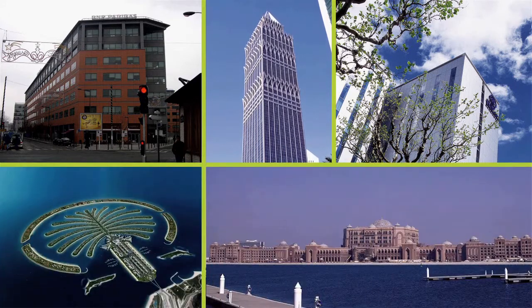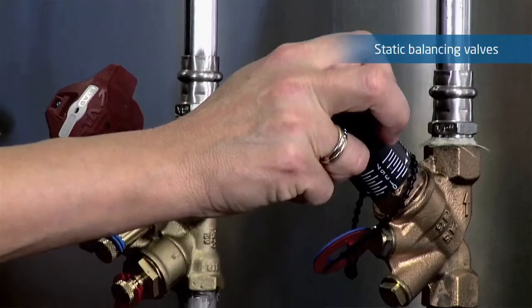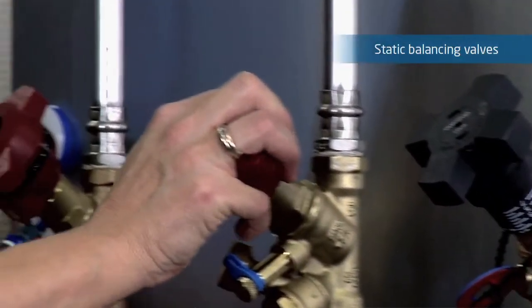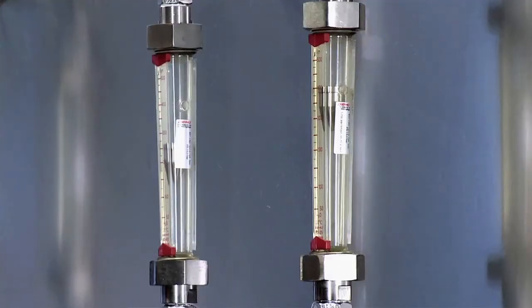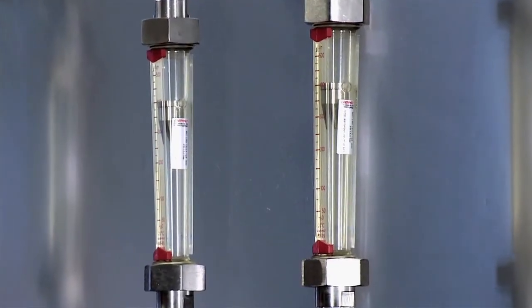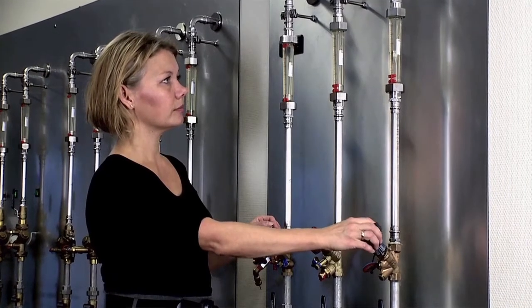How do those products help in saving energy and reducing carbon emissions? One of the modern trends in heating and cooling systems is the use of inverter drives on pumps and what we call two-port control valves on things like fan coils and air handling units. These are fine and great devices, which mean there is a potential for the energy consumption of the pumps to be reduced when the system's not fully occupied or where you haven't got extremes of outside air temperature.